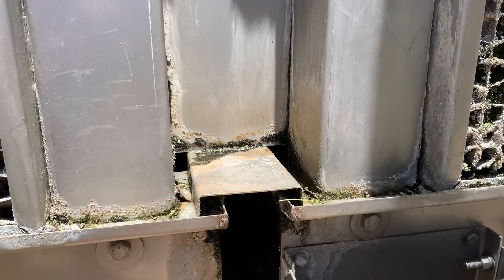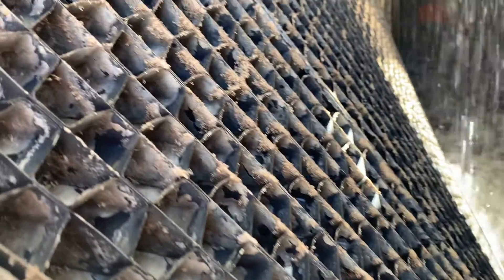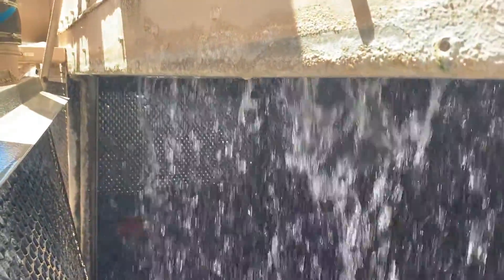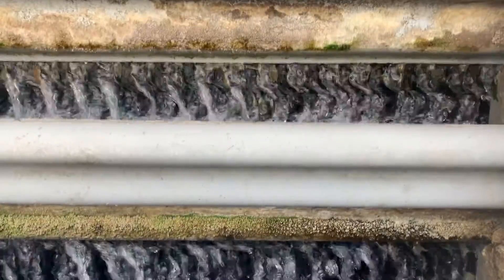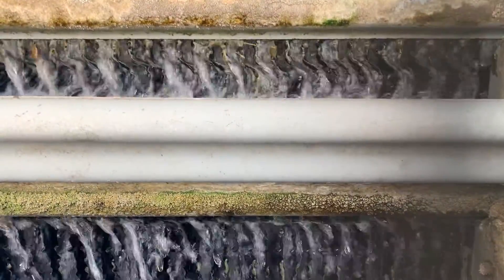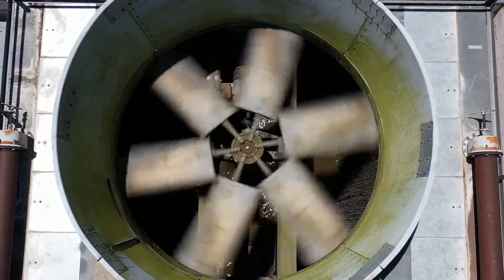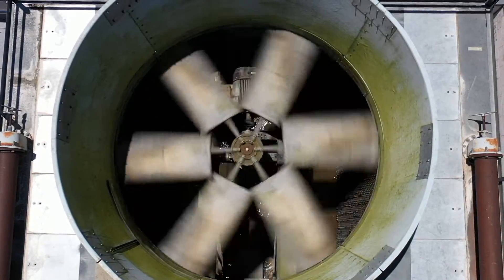Some purchasers choose to upgrade their basin and hardware to stainless steel. While limiting basin leaks, the ugly truth is mixing stainless steel with galvanized steel causes worse issues. The use of dissimilar metals in the wetted airstream leads to increased corrosion and scale, a superfood source for deadly Legionella bacteria to grow.